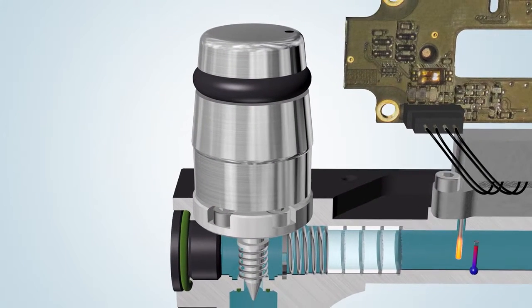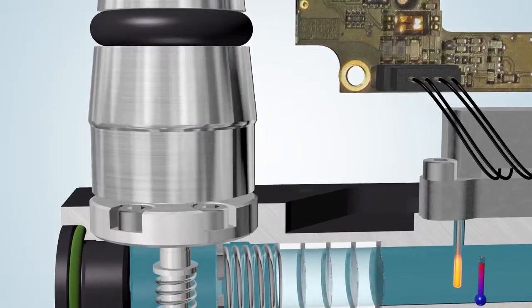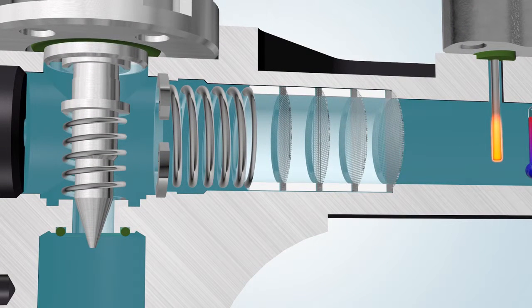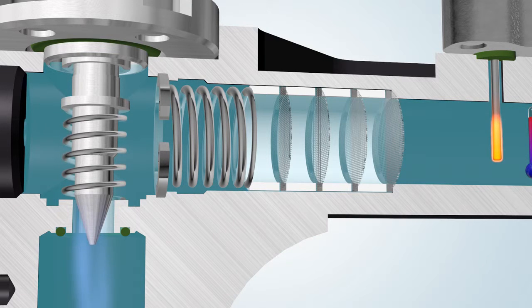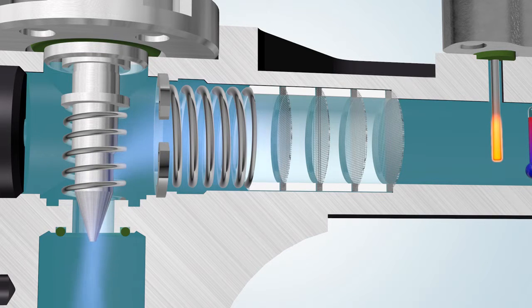Once the instrument has been connected to the process line and the pre-pressure has been set, the measured value corresponds with zero flow as long as the manually controlled needle valve is in a closed position. The needle valve, which has an orifice with a long tapered conical seat, makes it possible to regulate the flow rate. A needle-shaped plunger on the end of a screw exactly fits the seat. As the screw is turned and the plunger retracted, flow between the seat and the plunger increases. Since it takes many turns of the fine-threaded screw to retract the plunger, precise regulation of the flow rate is possible.